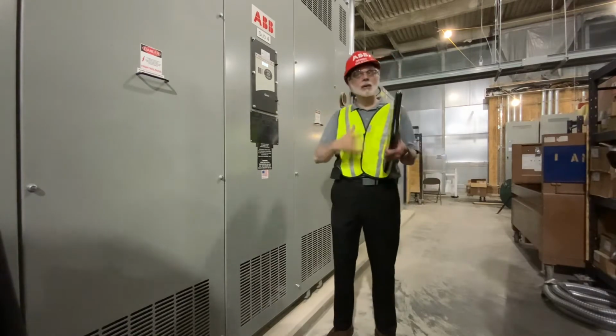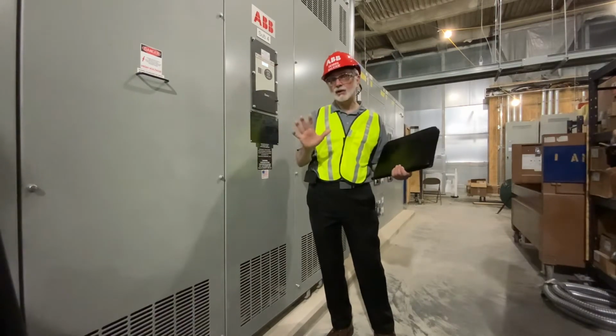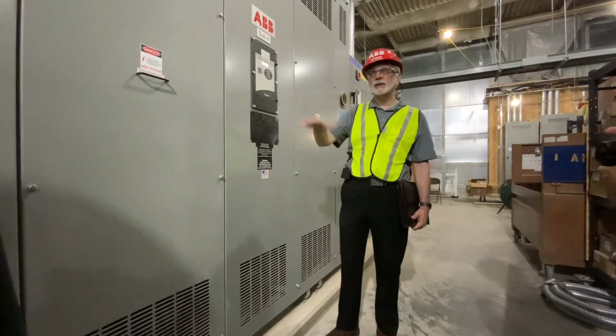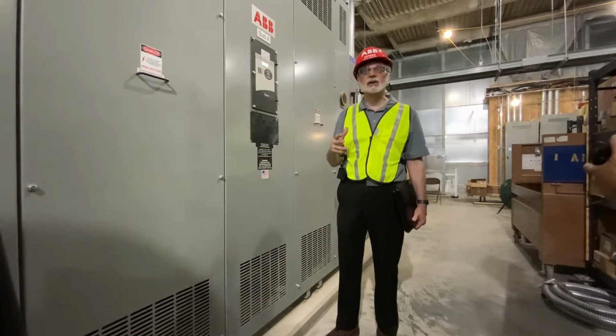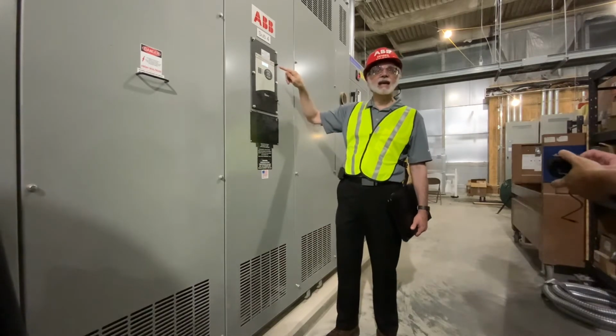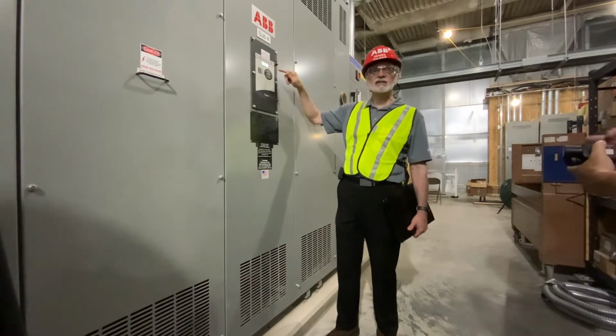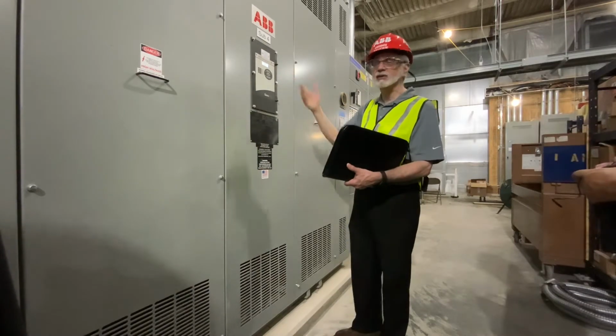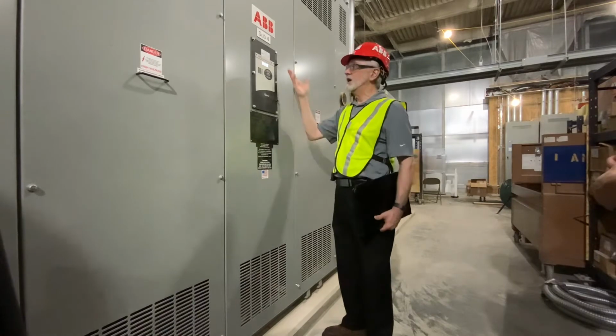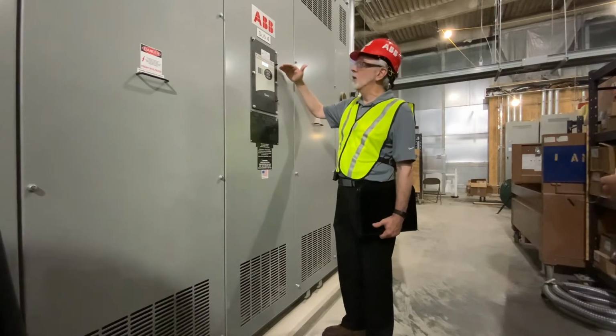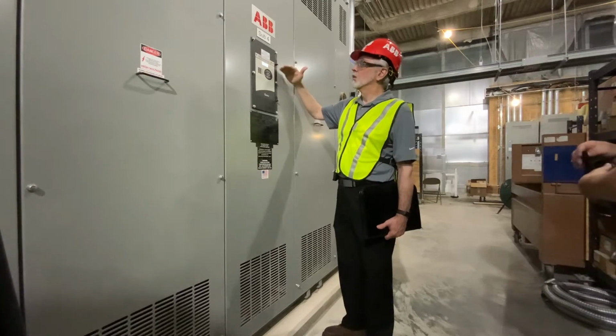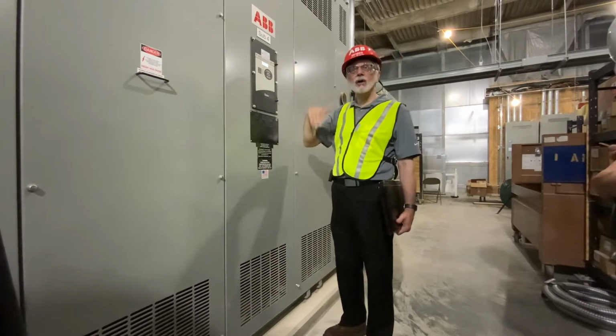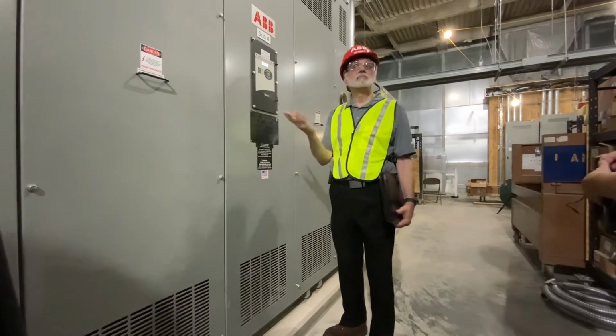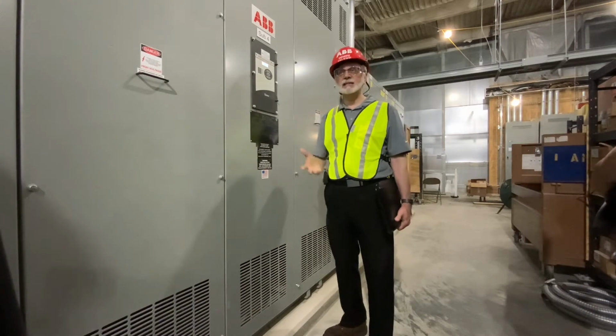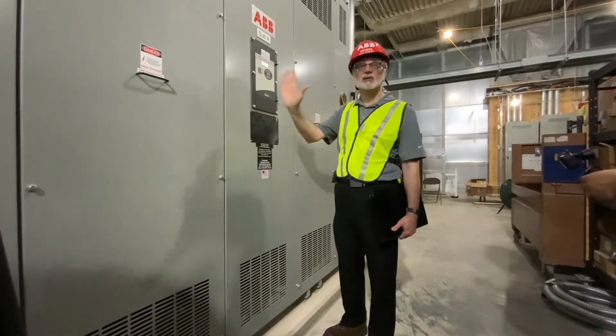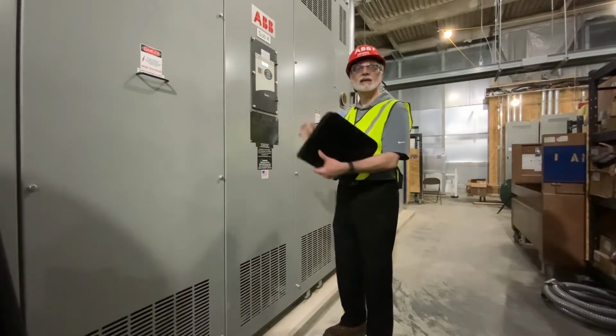So again, kind of going through the maintenance and looking out for the equipment, it might not be a bad idea when you're making your rounds to make sure that you're not seeing any abnormal spikes on the transformer temperature. You can see it automatically cycles through, so if you just stand here for probably a minute, you'll be able to see left, center, right, maximum. And if all those numbers are below 150, this transformer is doing well. It hasn't been stressed. The coils are being distributed equally. You're not getting any hot spots on the left or hot spots on the right.